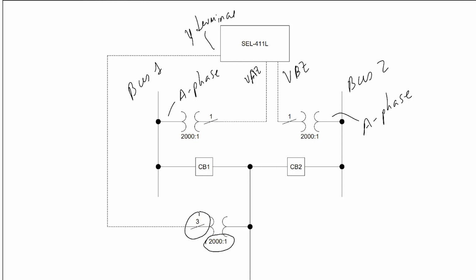Now, this is where things get a little bit complicated when we talk about the sync check element, because we could wire any of the three phases from bus 1 to the VAZ input of the relay, and the same is true for bus 2 as well. So we could wire B phase or C phase, or we can even wire the phase-to-phase voltages.